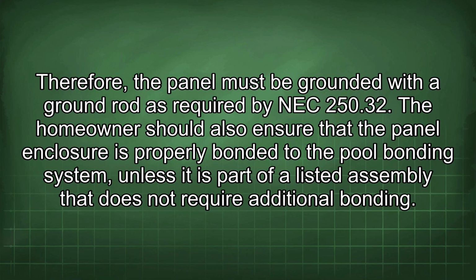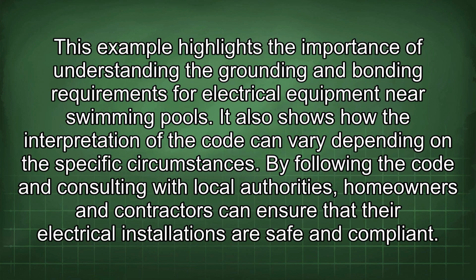250.32. The homeowner should also ensure that the panel enclosure is properly bonded to the pool bonding system, unless it is part of a listed assembly that does not require additional bonding. This example highlights the importance of understanding the grounding and bonding requirements for electrical equipment near swimming pools. It also shows how the interpretation of the code can vary depending on the specific circumstances.